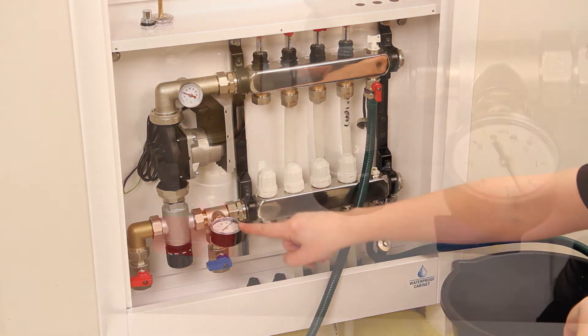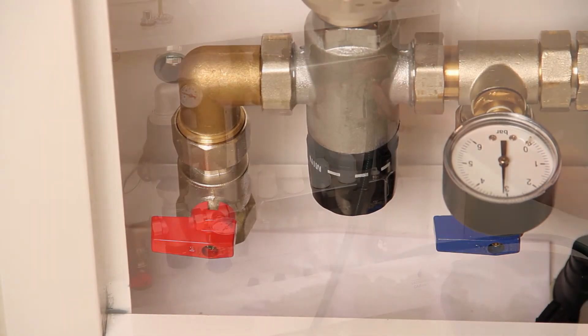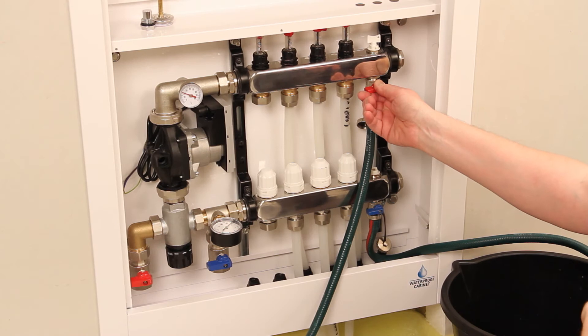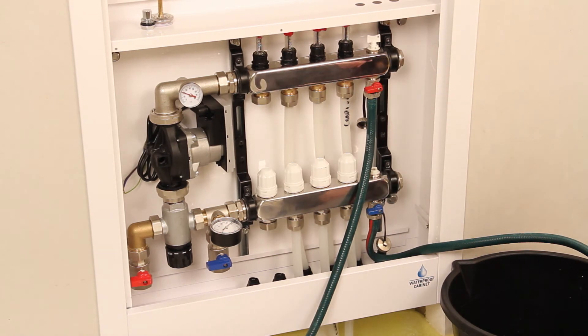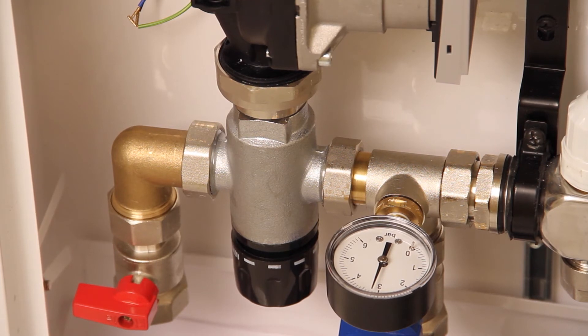The pressure gauge will start to climb. Allow the pressure to climb up to three or four bar and close the fill drain tap on the flow bar. This will seal the system and hold it under pressure test. You can now turn off the cold water hose supply.